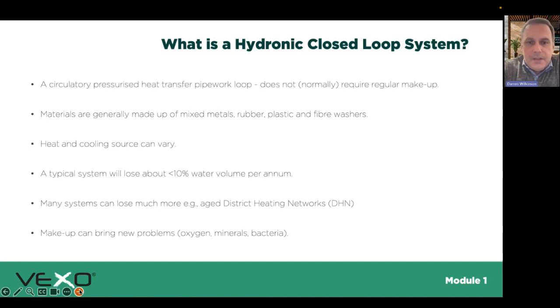Typically you can lose around 10% of the system volume over the course of a year, regardless that it's a sealed system, and some systems can lose much more. There's plenty of aged systems out there at universities and hospitals that lose a lot more water.